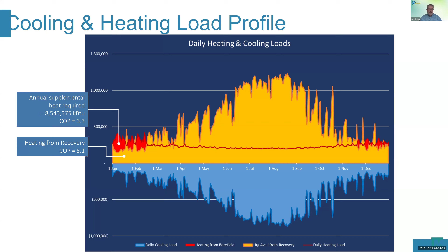In the old days, with pneumatic controls, we had to keep things separate. A heating system was its own system, with control essentially limited to a mechanical linkage adjustment on the burner, and a chiller just ran, rejecting all its heat elsewhere. We treated these as entirely separate systems. But with modern control systems, we can bring them together and create a single plant that does both heating and cooling without any gas-fired equipment.